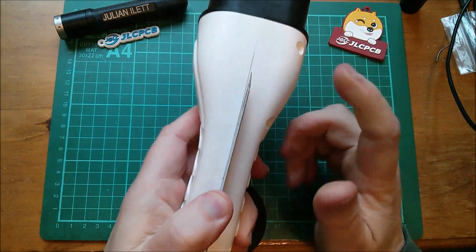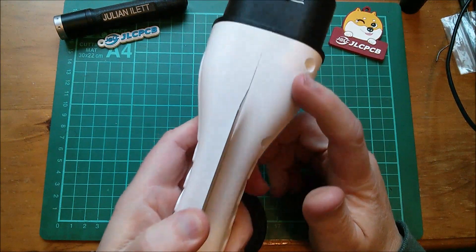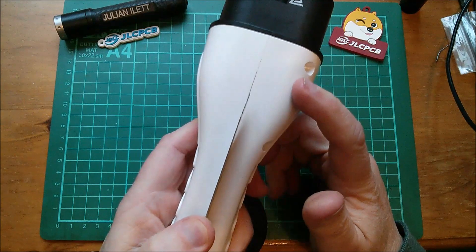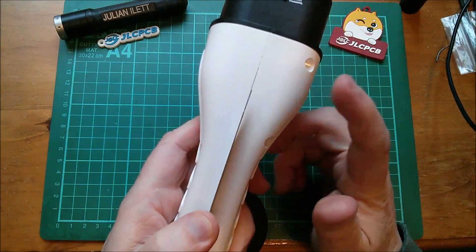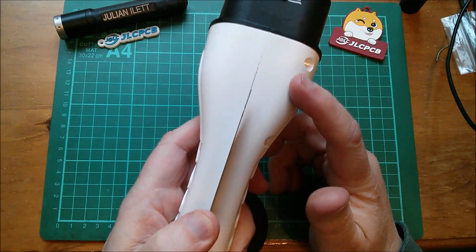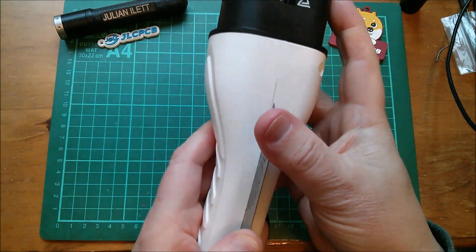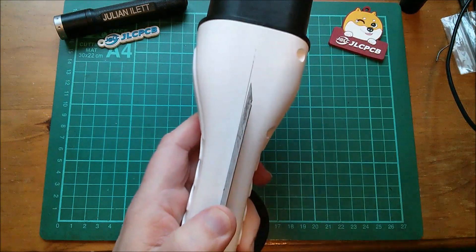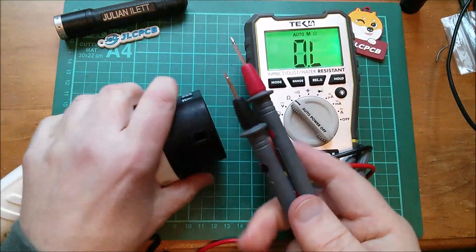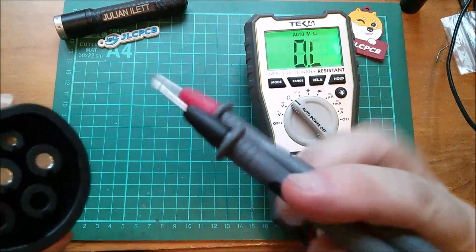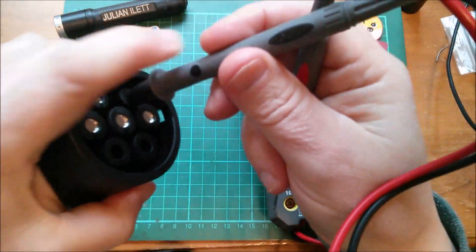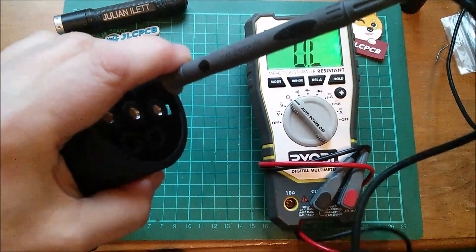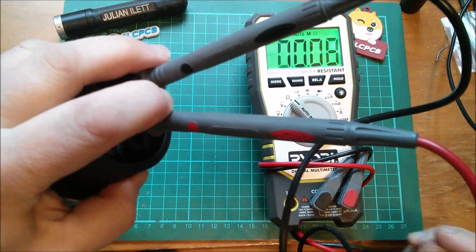Now this is a 16 amp or up to 16 amp EVSE. So it should have the 20 amp rated resistor, which would be 680 ohms. And in fact, we can measure it.